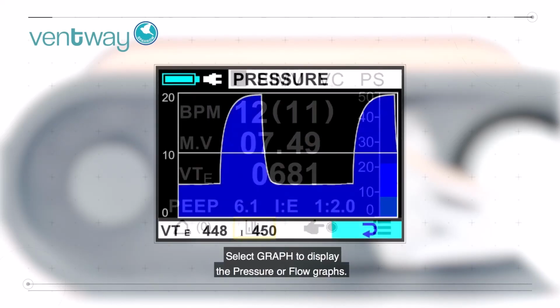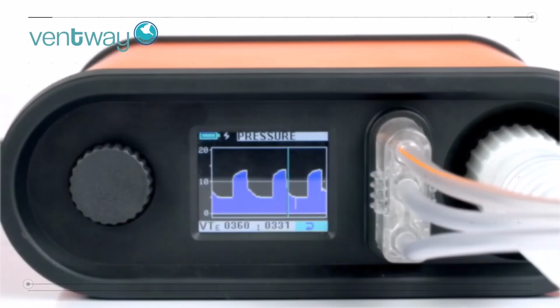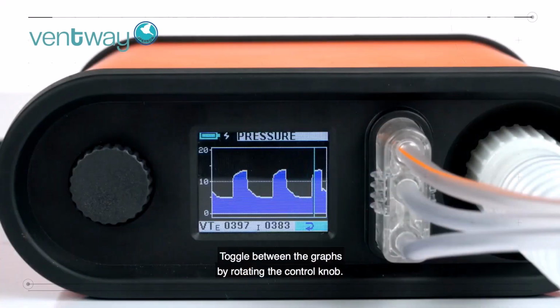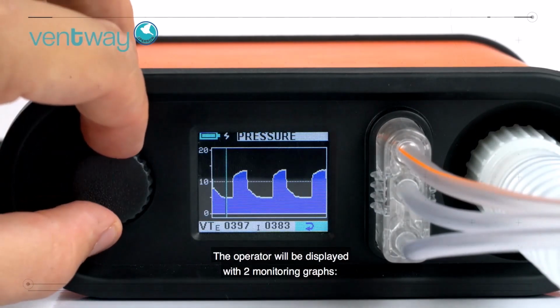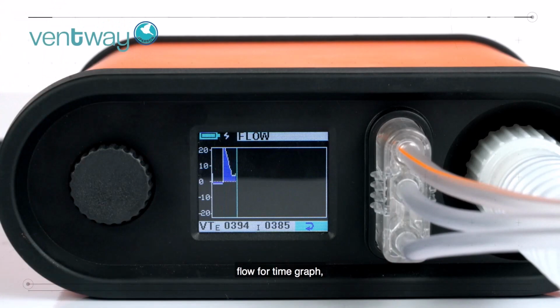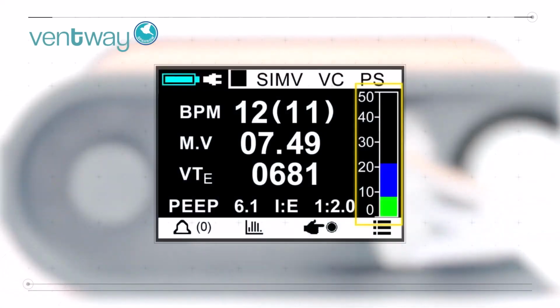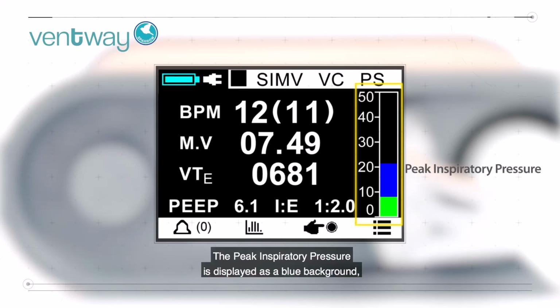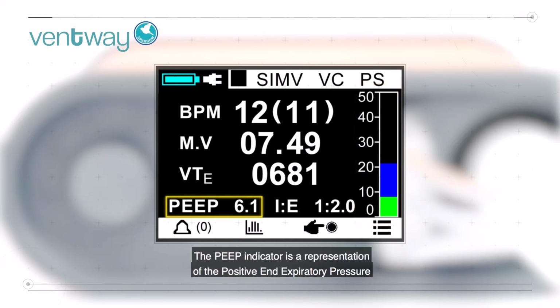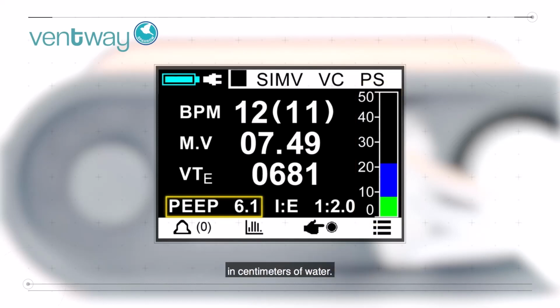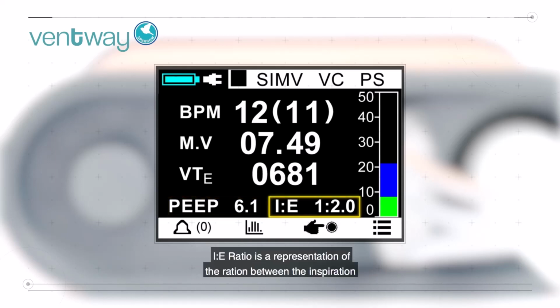Select Graph to display the pressure or flow graphs. Toggle between the graphs by rotating the control knob. The operator will be displayed with two monitoring graphs: Flow over time graph, Pressure over time graph. Patient pressure is displayed to the user by a bar. The sample rate of the pressure value is 500 Hz. The peak inspiratory pressure is displayed as a blue background, remaining throughout the current breath, while the current pressure is displayed in green. The PEEP indicator is a representation of the positive end expiratory pressure in centimeters of water. I to E ratio is a representation of the ratio between the inspiration and expiration duration.